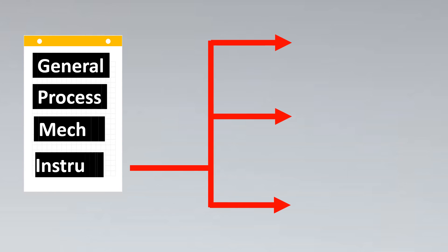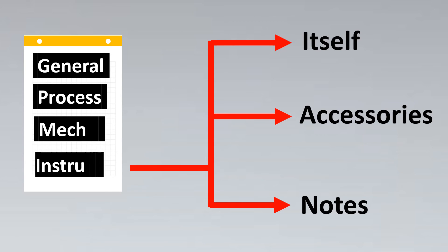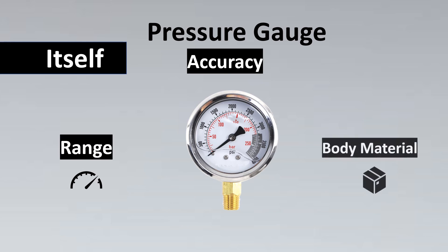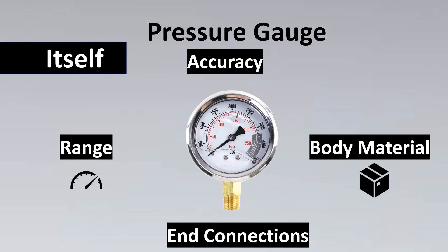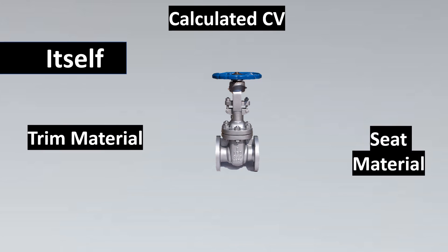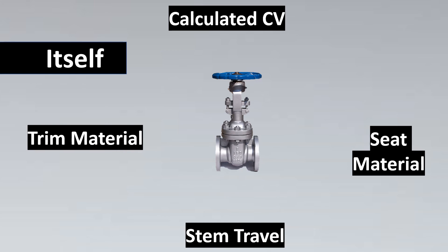The instrumentation part can be broken into three sub-parts: the instrument itself, its accessories, and the notes section. The instrument itself includes its own components — for example, for a pressure gauge: accuracy, range, body material, and end connections such as threaded or flanged. For a control valve, it could include the calculated Cv, trim material, seat material, stem travel, etc. This varies from instrument to instrument and is captured in the form type.